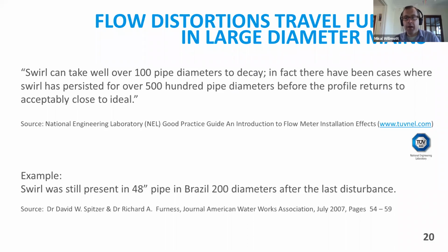There's a really, really good case study of this in the American Waterworks Association Journal, done by Dr. Dick Furness, who went down to Brazil. I don't have time to go into the whole case study, but he looked at a 48-inch pipe in Brazil coming out of a pump station, and he found some really good evidence that swirl was still present in that pipe 200 diameters after the last disturbance. So what we're seeing in big pipes is that we get poor hydraulics, or distorted flows going on for possibly hundreds and hundreds of diameters.